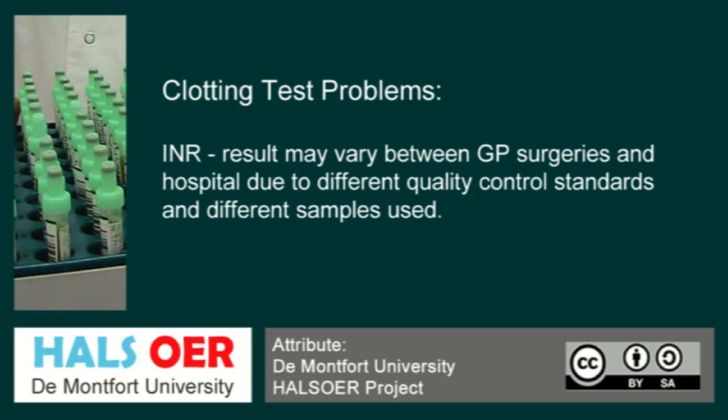One of the problems we encounter is with GP surgeries — they may perform an INR and get a result of 2 or 3, but when they send it to the hospital here, we may find the actual sample has an elevated INR and they can't understand why. Our analyzers are very well maintained because of the QC materials we perform regularly, with a QC run every 2 to 3 hours. Our technology is very different from what GPs use, which are endpoint detectors using whole blood. We use plasma, which is much more accurate and doesn't get affected by human variables at all.